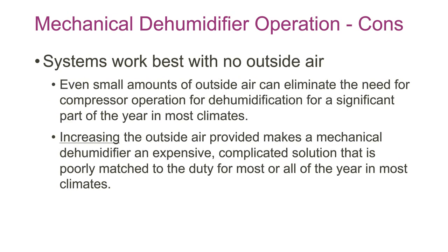On the downside, they really work best with no fresh air at all. Even small amounts of fresh air can eliminate the need for compressor operation for dehumidification for a significant amount of the year, and if that's done, then you have a machine that can't really do what its benefit is. And if you increase the outside air, it makes it really an expensive, complicated solution that really isn't matched to the duty for a lot of the year.